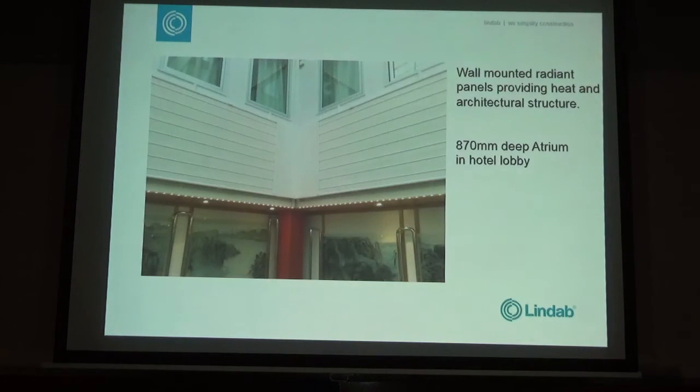Surface mounted, vertical. Okay, so again, you get more output from the vertical panel. Your proportion of radiant and convective changes, so it becomes 50-50. So your output goes up, and the proportion of radiant to convective changes. So this, as you said before, 350 watts becomes 175.